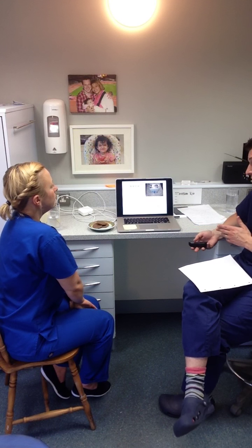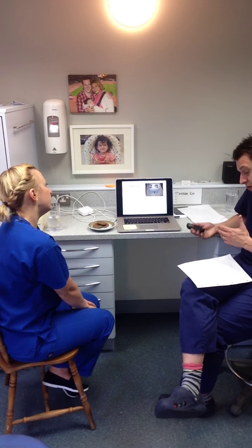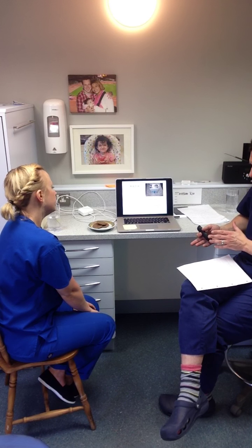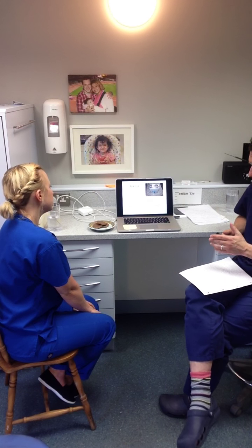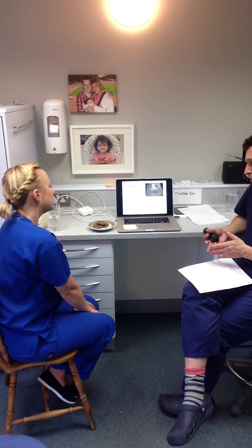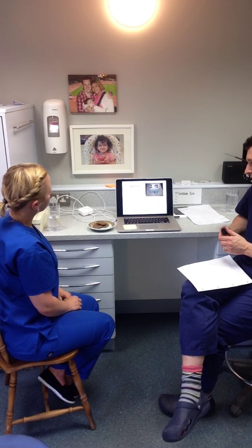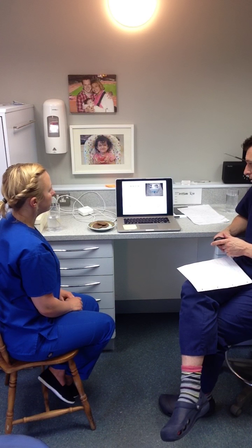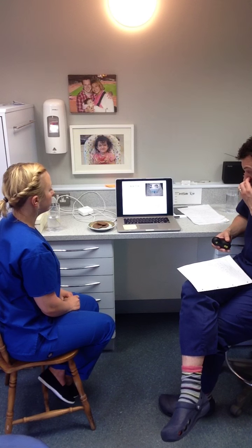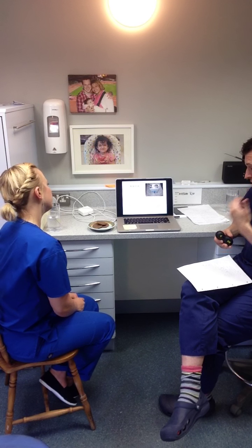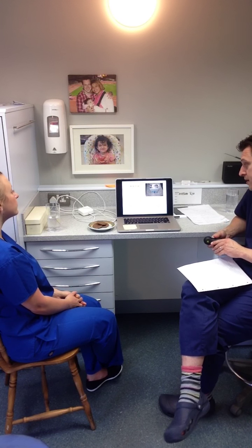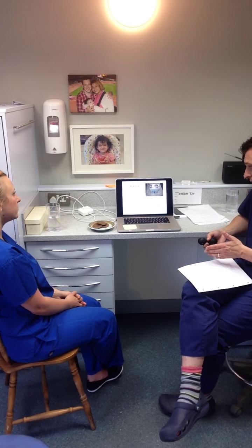Not as effective is the ultrasonic bath cleaning. You can validate this to a point, but it's not as concrete and belt and braces as, say, the washer disinfector is. It's really important to change the water and maintain the unit regularly. It's proven to enhance debris removal compared to manual cleaning. It's frequently tested according to the manufacturer's instructions to make sure that the water's been agitated sufficiently. And the instrument should be immersed in the cleaning solution.